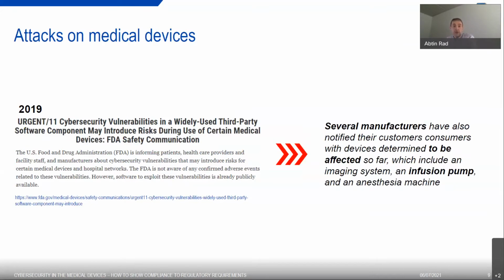And the interesting part here is that the devices where this software component was incorporated were developed taking into account cybersecurity measures. However, as time passes, new vulnerabilities have been identified in this software component that open doors to new attack vectors. The learning here should be that even if your device is secure at the point of release, it doesn't mean it will be secure over the few years that the device is being used in the market. So post-market activities in regard to cybersecurity are necessary, and you need to consider them in your development lifecycle.